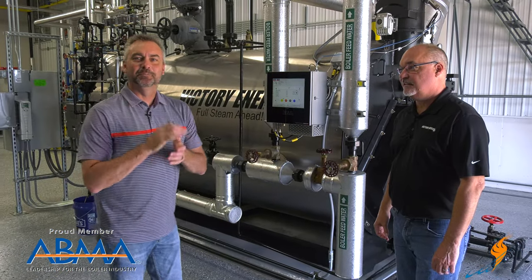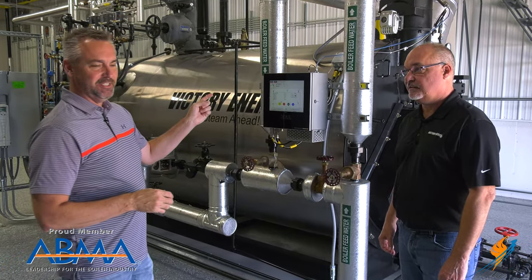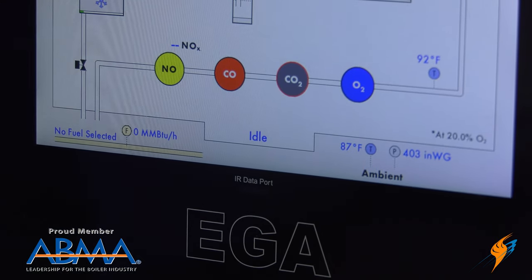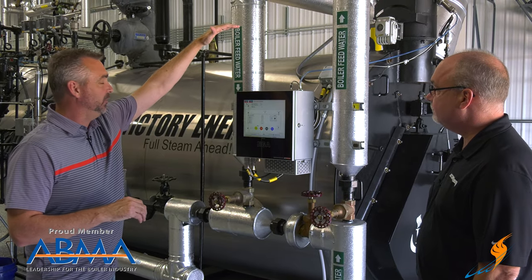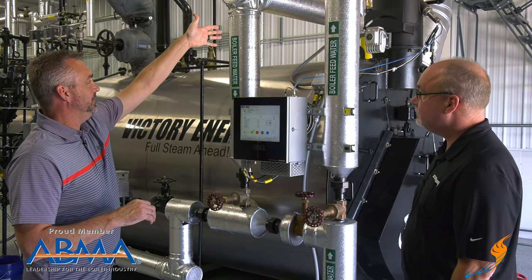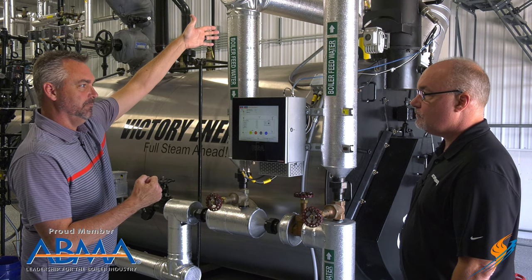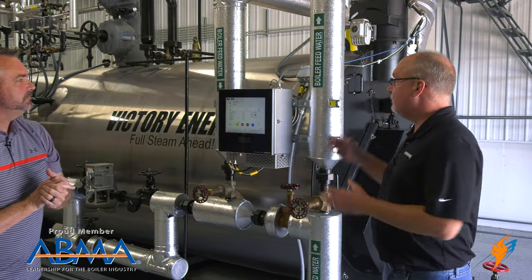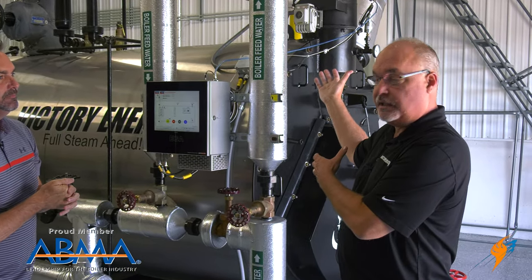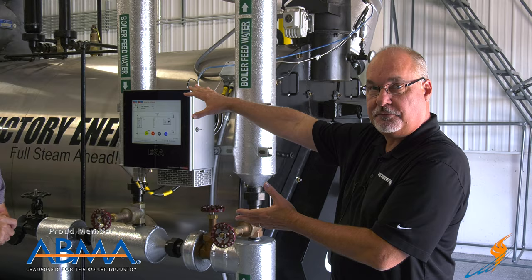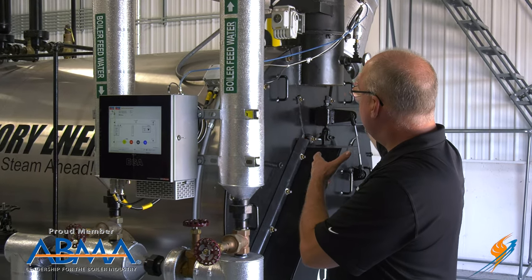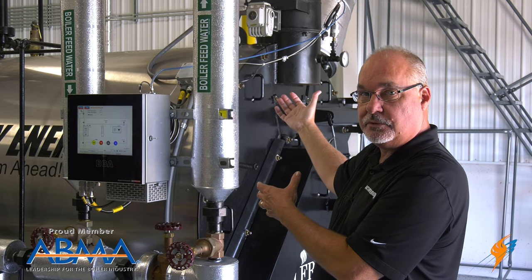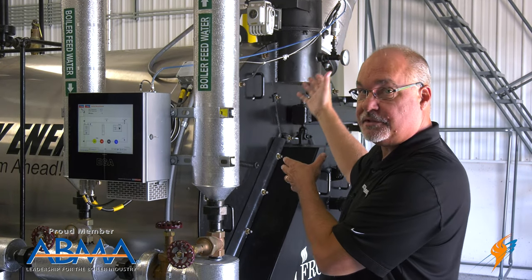We've come back to the back of the boiler where we have our EGA — our exhaust gas analyzer — and this is where the stacks are as well. This is really where we're actually analyzing the oxygen and getting our feedback on the oxygen going out the stack. We're in the back because that's where the stack is here, though it could be a two or four pass and would be in the front. The point is that you do your O2 measurement and any other combustion analysis from the stack.